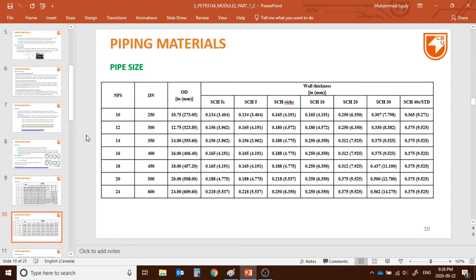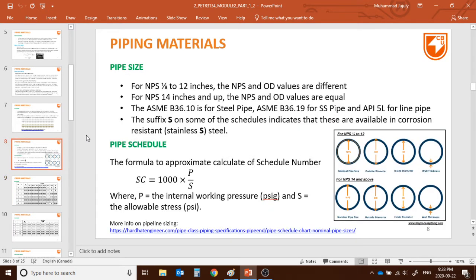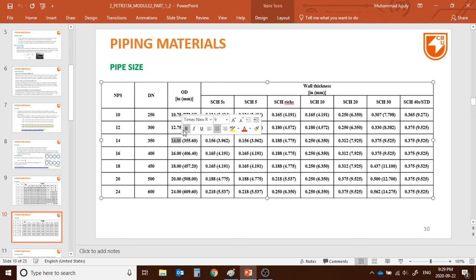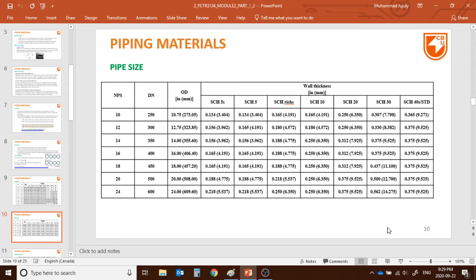So for example, if told to define a pipeline with NPS 14 and schedule 40: going to the chart, NPS 14 means the diameter is 14 inches (355.6 mm), and schedule 40 means the thickness is 0.375 inch (9.525 mm). This will be used frequently throughout the course.